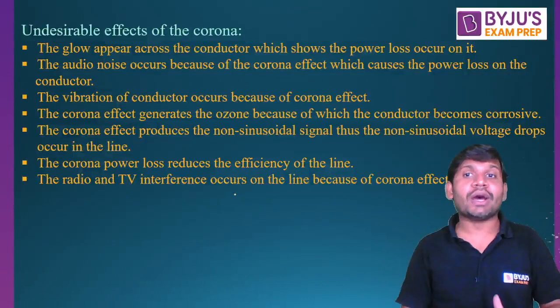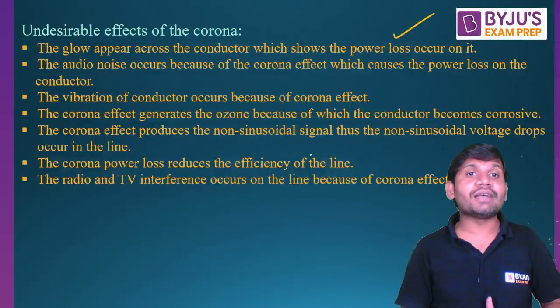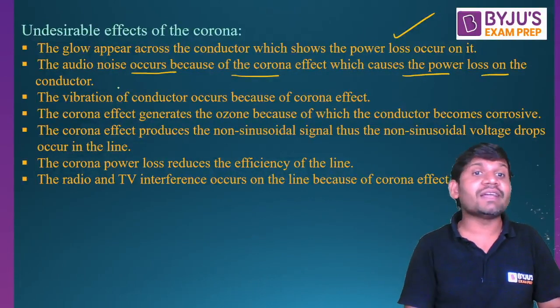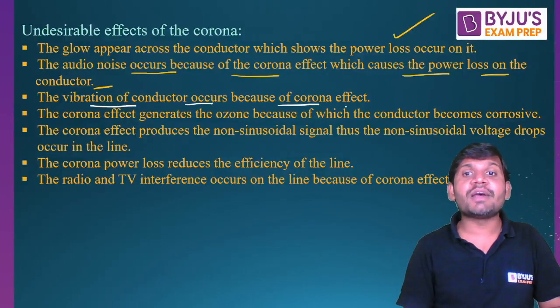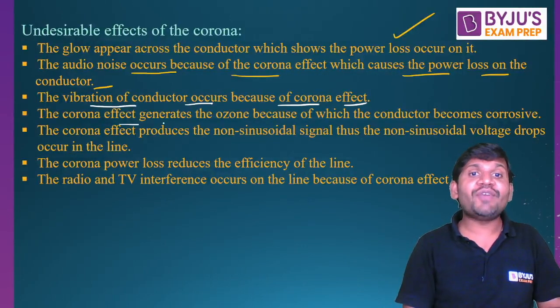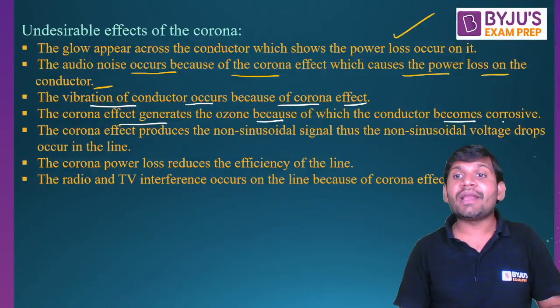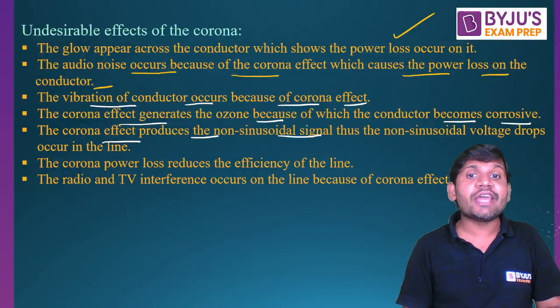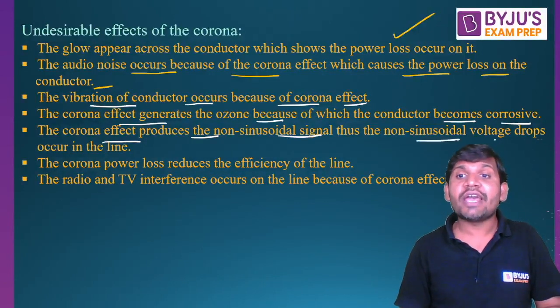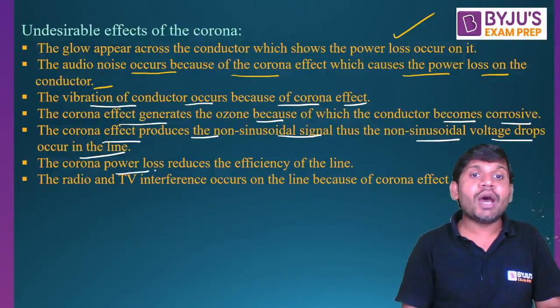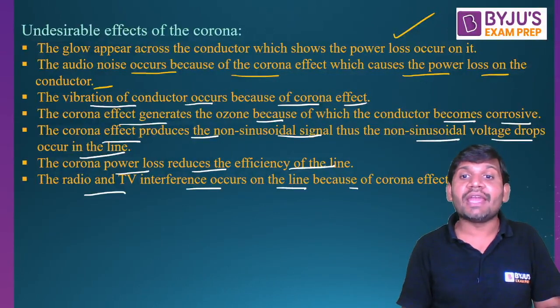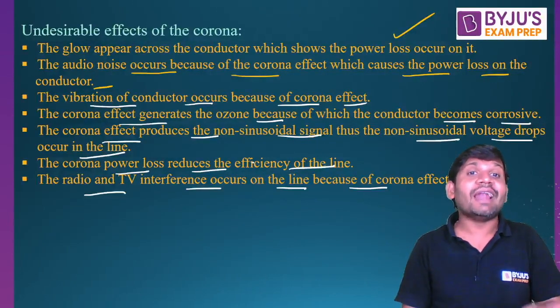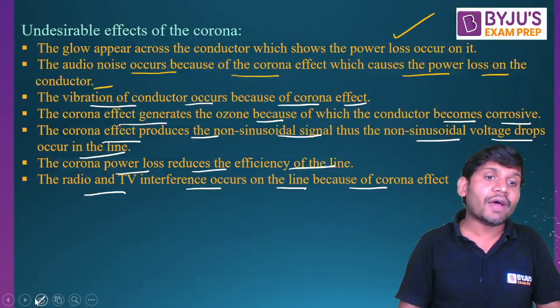What are the undesirable effects of corona? Corona causes power losses. Audio noise occurs because of the corona effect, which causes power loss on the conductor. The vibration of conductors occurs because of the corona effect. Corona effect generates ozone, because of which the conductor becomes corrosive. The corona effect produces a non-sinusoidal signal, so non-sinusoidal voltage drops occur in the line. Corona power loss reduces the efficiency of the line. Radio and TV interference occurs on the line because of the corona effect.